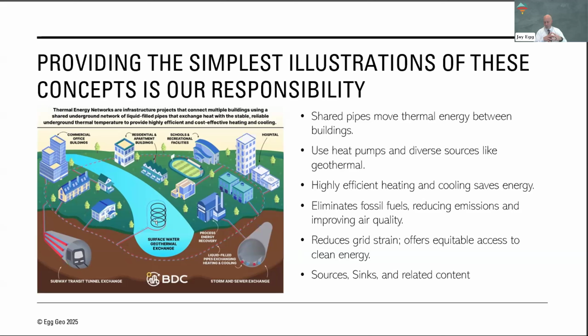One important thing to understand with these systems is that, as a group of buildings, most of the time they're cooling dominant—in balance, they have more heat to get rid of than they need. So in the summertime, our biggest challenge is moving heat out of these buildings, and in the wintertime, our biggest challenge is moving heat from building to building. That's why energy networks are important.